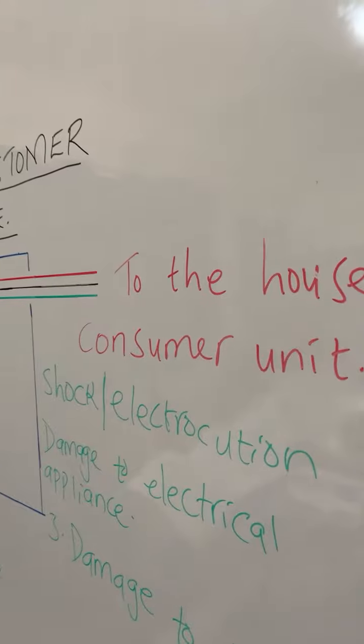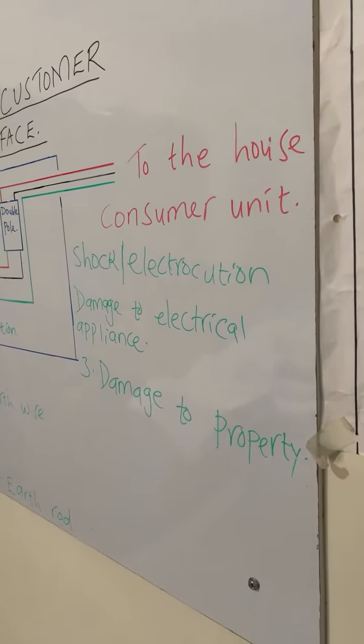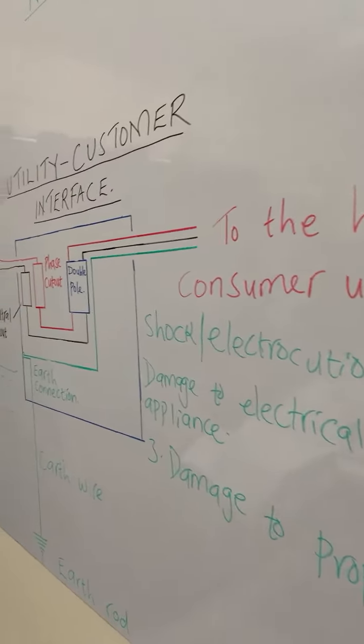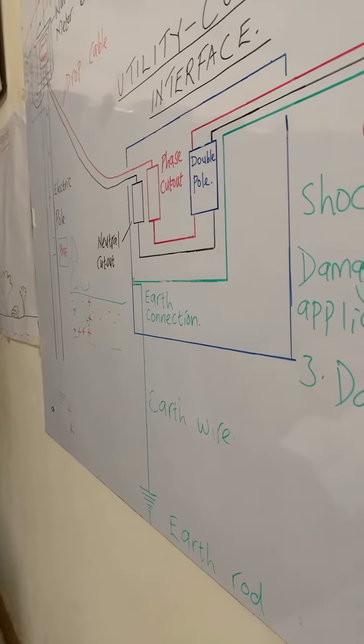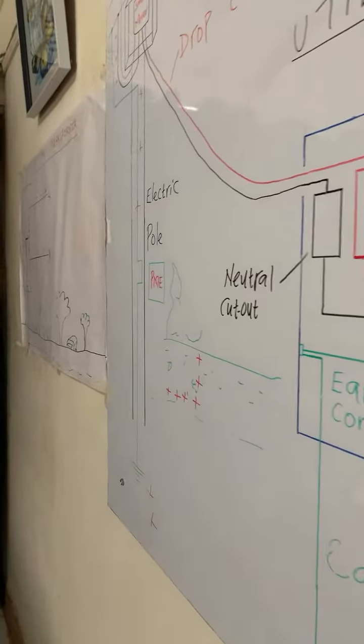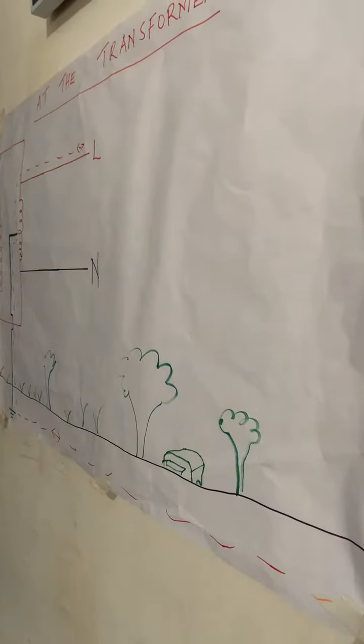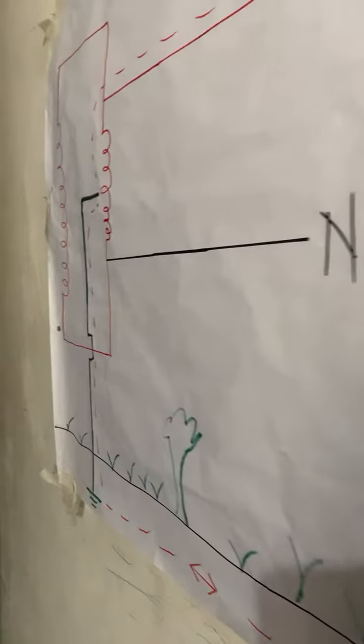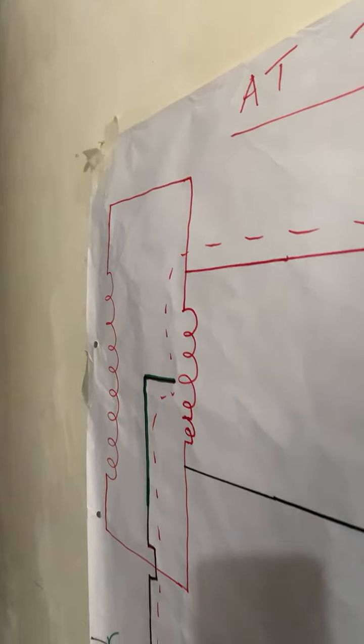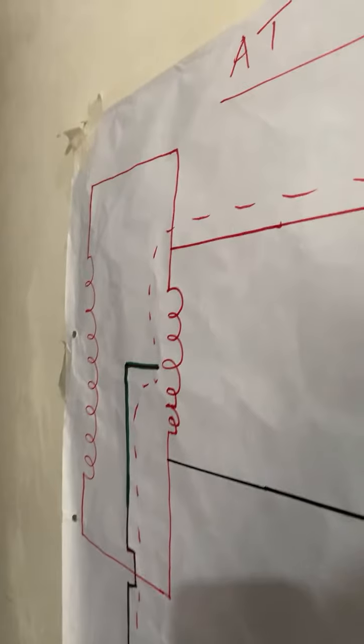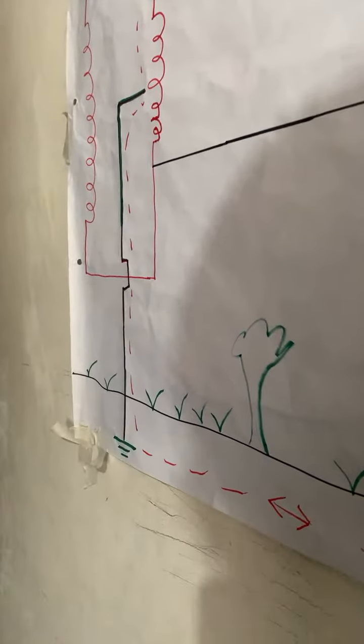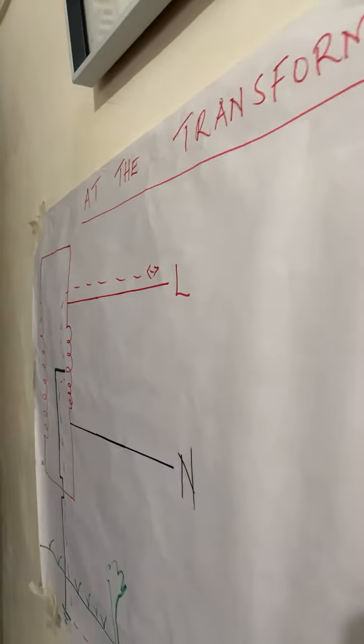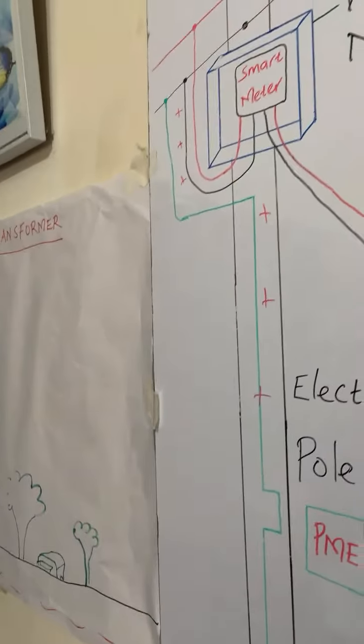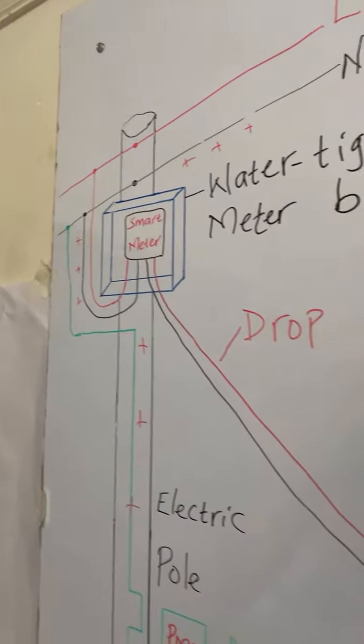The bottom line is that all the wiring done at the consumer unit is redirected to the ground through the earth rod, which is installed in any electrical installation, whether it is single phase or three phase. We'll also be tackling how that earthing works all the way back to the transformer. This is a transformer here, and that is a demonstration of the coil or the winding. How is the earthing connected all the way to the transformer, getting back to the electrical flow of that phase connection, whether single phase or three phase?